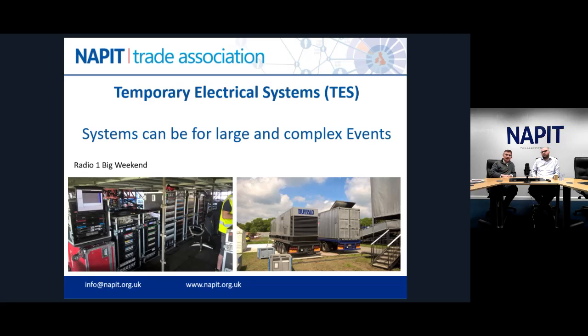On the right-hand side, you can see the containerized generators. And in events, we often run generators in synchronized parallel pairs so that if a generator fails, you don't lose the whole show. So each trailer has got a pair of generators running in parallel. On the left-hand side, you've got two 800 kVA units, and on the right, you've got two 900s. One is just doing the outside broadcast, and the other is doing the lighting and stage power for video and sound and so on.